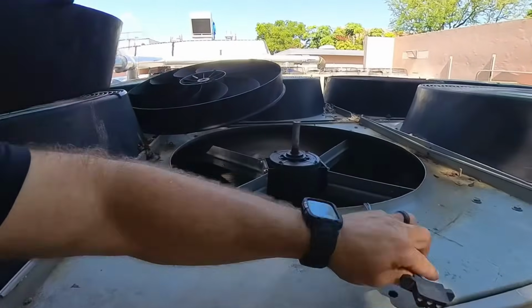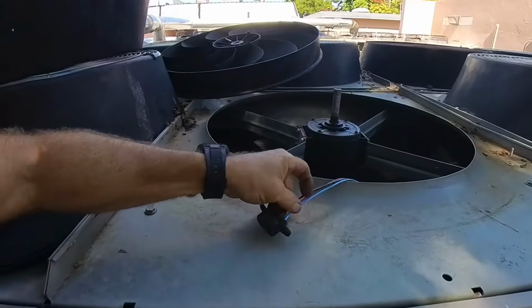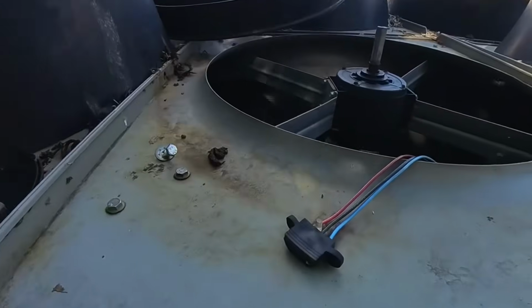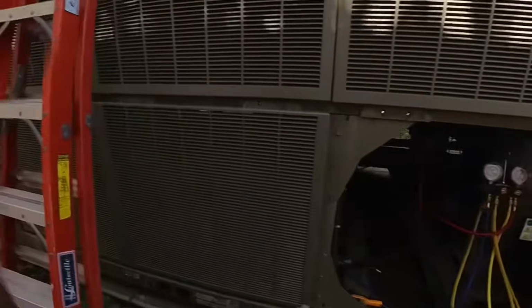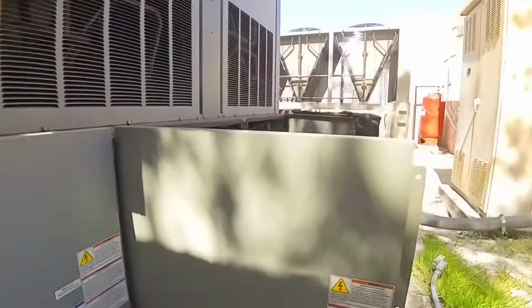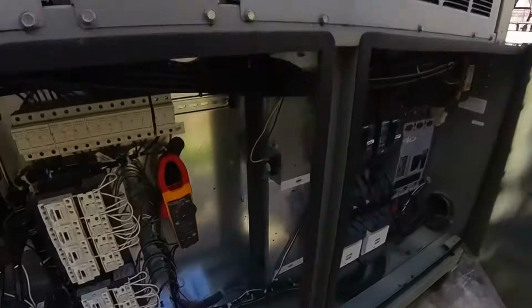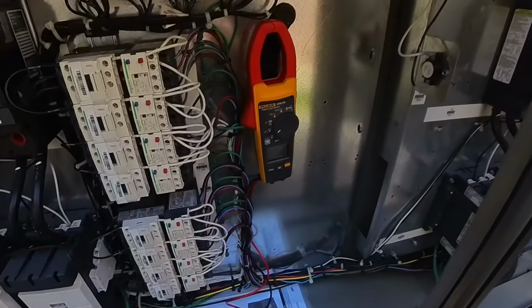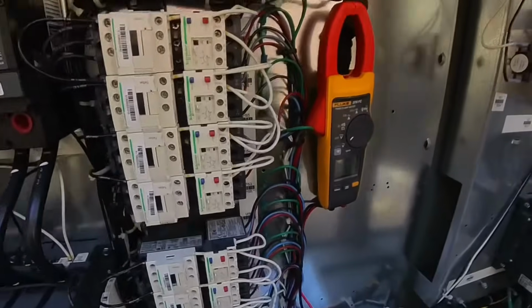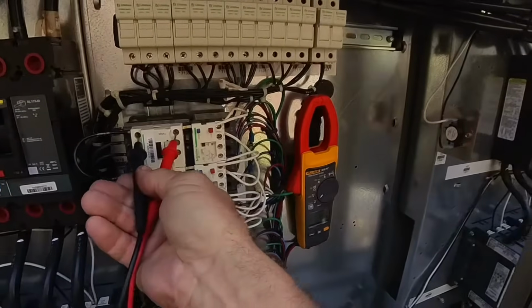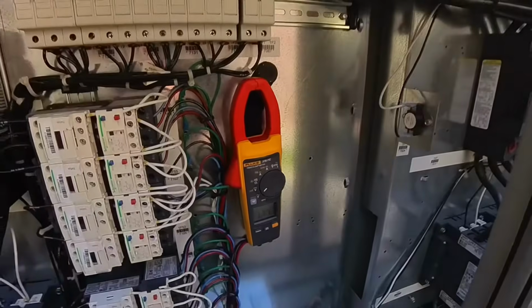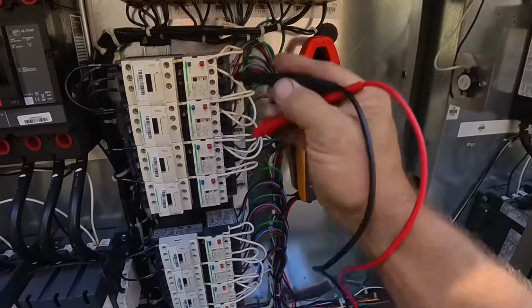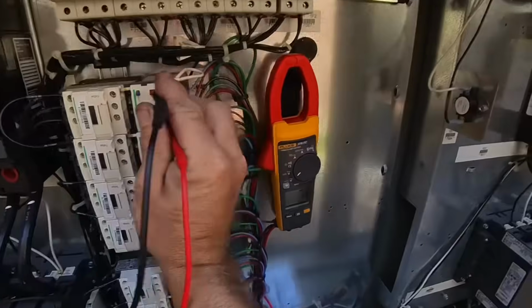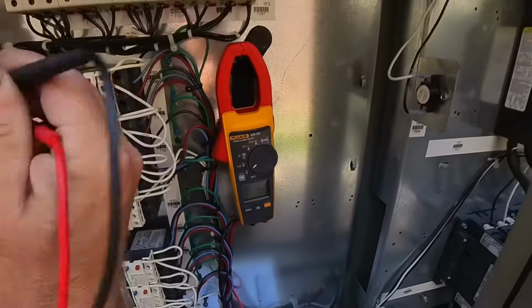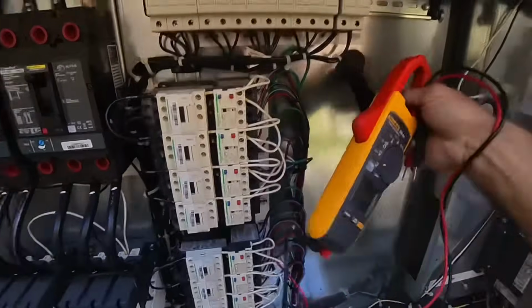Yeah, it's trying to. It won't move now. All right, let's go down. Reset that. It engaged. We now have 120 volts on our coil, and our overload is now closed, so we should have voltage at that plug.